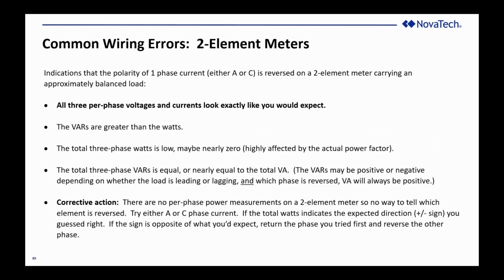All right, so let's look at a couple examples. There are fewer of these. We're almost done. Let's say one phase current, either A or C, because you only have two elements, is reversed. If you reverse the B phase, it wouldn't make any difference because the B phase doesn't enter into the watts. So all three per phase voltage and per phase current will look exactly like you'd expect. The VARs will be greater than the watts, which is one indication you've got a problem. Total three-phase watts is a low number.